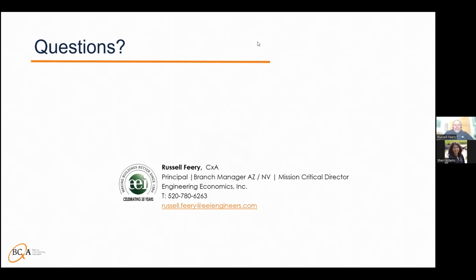Looks like there's another question, says, did you find any instances where the VAV was fighting with the chilled beams? No, in the particular project that we had highlighted there, we had not seen any issues. Our approach was to do the VAV testing prior to the chilled beam testing so that we could make sure that the upstream air delivery was functioning per the sequence of operation. So we did not see any of that, but the potential is there.